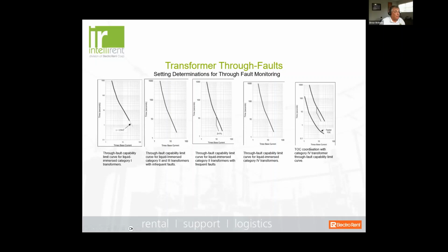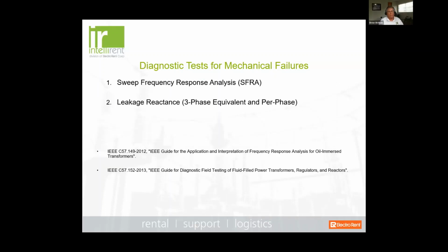And then in some cases, you have to coordinate that with your overcurrent settings on a distribution relay. The most important thing, though, when you go to set your through fault monitor, is to check with your OEM on the withstand capabilities for that particular transformer. Now, if we've recognized that we've had a through fault on a transformer, or the alarm has gone off, or you've noticed during your periodic routine testing that we've had a number of through faults, maybe it's important for us to check our diagnostic testing to see if we've had any mechanical failures.